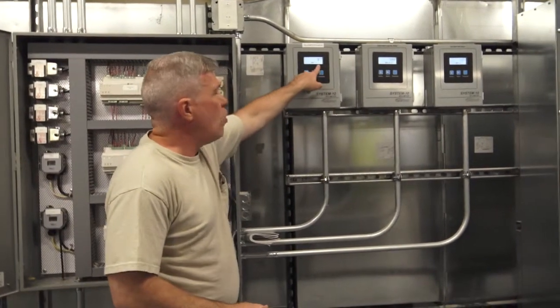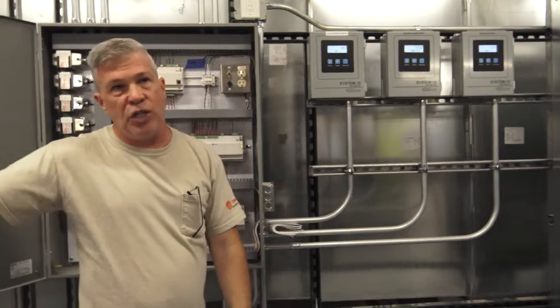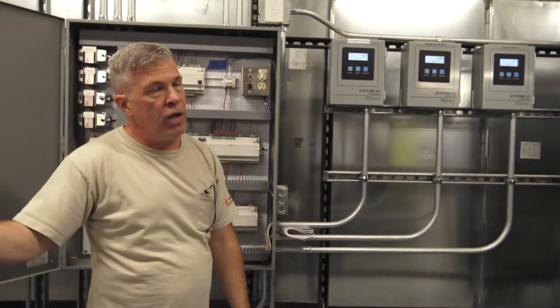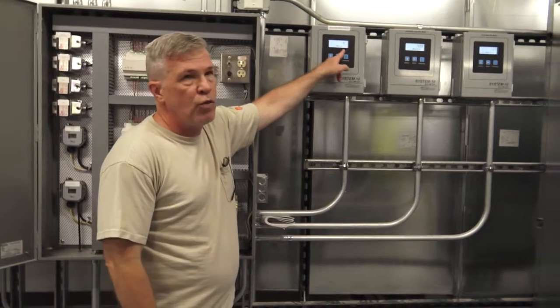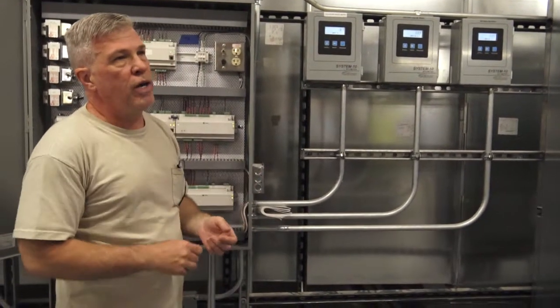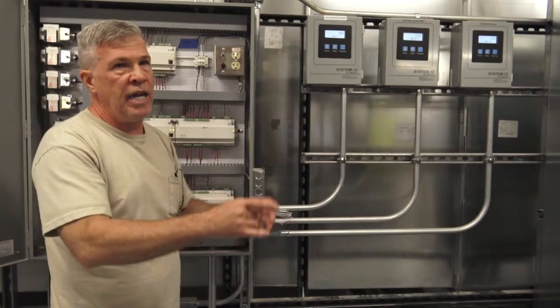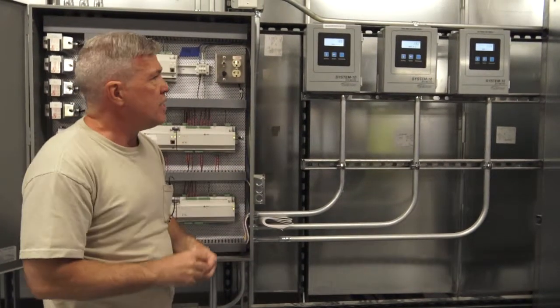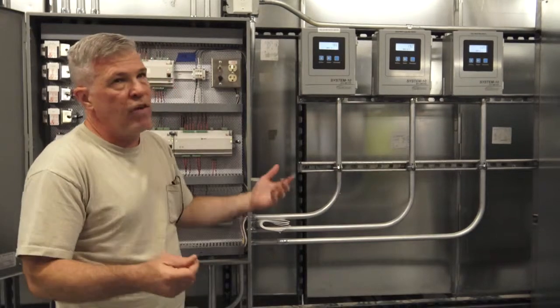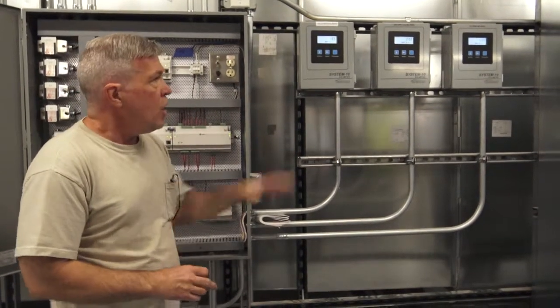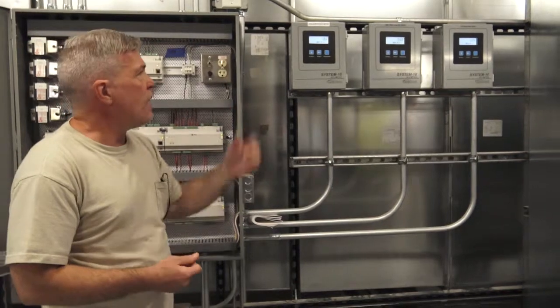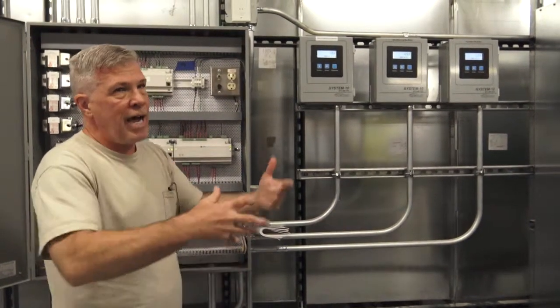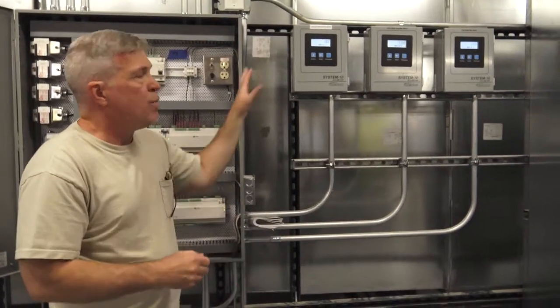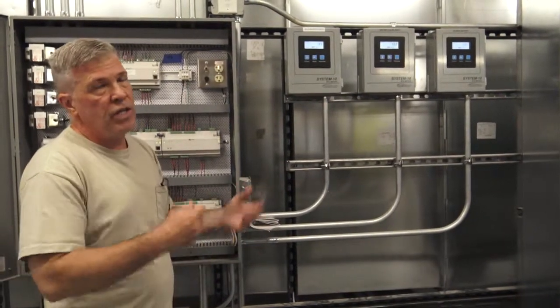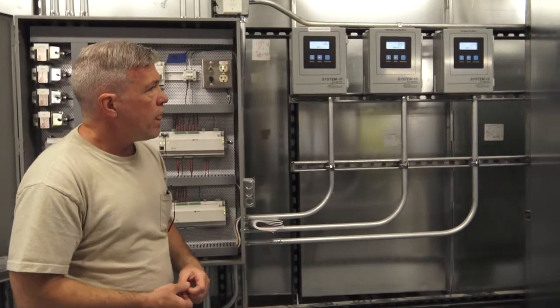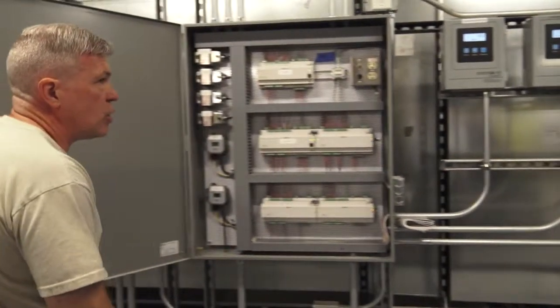The chill water one will vary based on the air handler chill water valve, for the most part. As that valve opens and closes, you'll see this rate change. It does also serve the blower coils and the linac, but that's a lot less flow. So primarily that creates the change. And the hot water is basically just driven off of VAV hot water demand. So they will all change. Not too often you'll see them set. Once your building gets occupied and the load settles down, these may not vary very much, other than seasonally. So that's basically the wall here for all the controls.